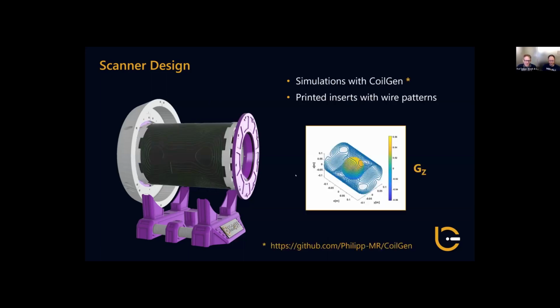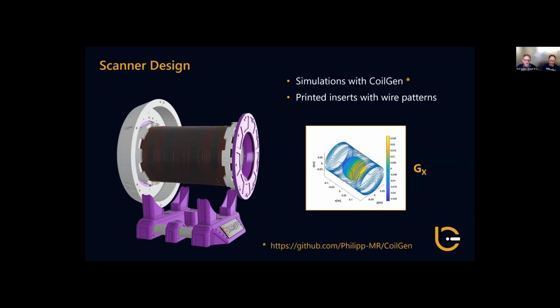And then below that, we have the gradient coils for the Z, X, and Y direction. And these gradient coils were simulated and calculated using the CoilGen software that has been developed by University of Freiburg. So this software, you can access it using this link here, was used to calculate these wire patterns. And then holders were 3D printed, which have the wire patterns imprinted, so that it was then possible to kind of glue copper wire into the imprints of these prints. And this is the gradient coil in the Z direction. This is the gradient coil in the Y direction. And then this is the gradient coil in the X direction.